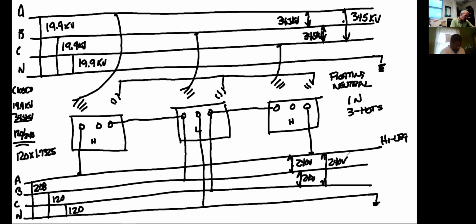The thing is, on the closed delta, and I'm going by the picture that we had before, A is now my high leg. You got to know which ones are your high leg transformers, and that's what I'm connected to. On open delta, it was C. Closed delta, it's A. Watch out for that when you're doing this calculation, 120 times 1.7325, or whatever the phase to ground voltage is, to get your high leg voltage. A lot of people trip up on that.